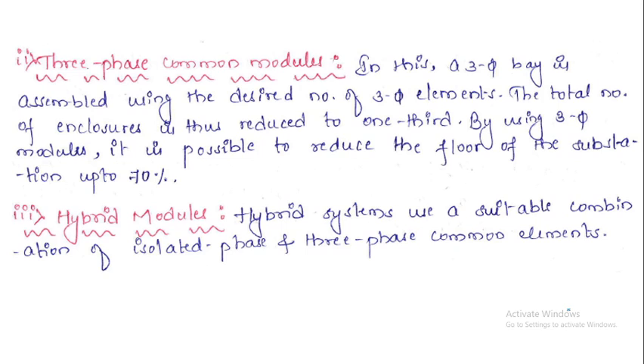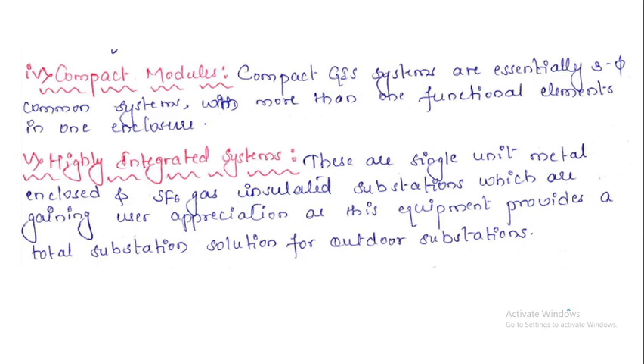Earlier we used to have a separate enclosure for each unit. Here in this common three-phase module, combining the three modules, we will have a single enclosure. So the total number of enclosures will be drastically reduced to 1/3. By using a three-phase module, it is possible to reduce the floor space of the substation by up to 70%. Then we have the hybrid module, which is nothing but a combination of isolated phase and three-phase common elements. Then we have the compact module.